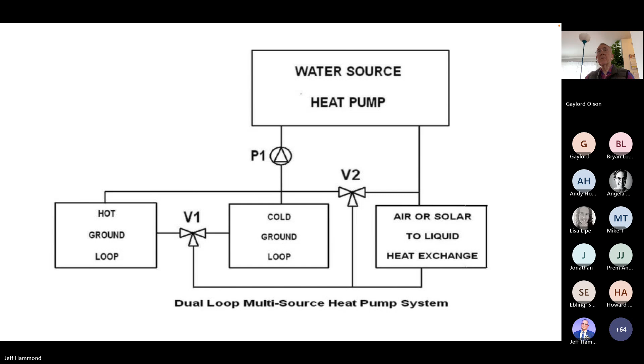we're showing here the direction that water will flow in those valves when you have the different modes of operation. So the air source mode is, oh, by the way, the darkening of the triangles in the valves shows the ports where water can flow in or out. If the triangle of the valve is not darkened, that means that no water can flow in or out of that port of the valve. So the air source mode allows water to flow from the heat pump down into the air to liquid heat exchanger and then back up through pump P1 and to the heat pump, but no water will flow into either ground loop. So that's the air source mode.